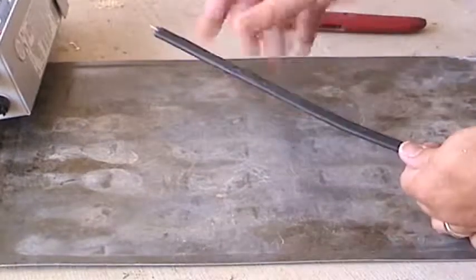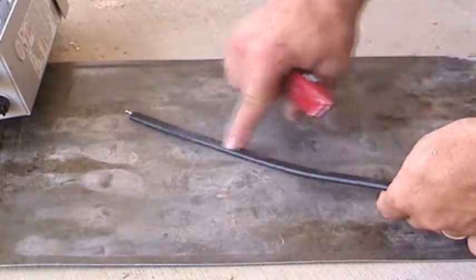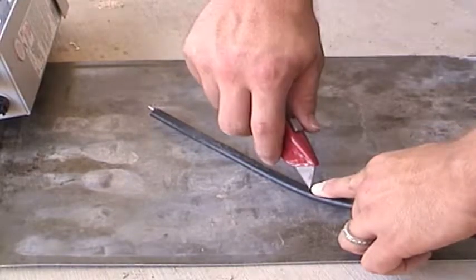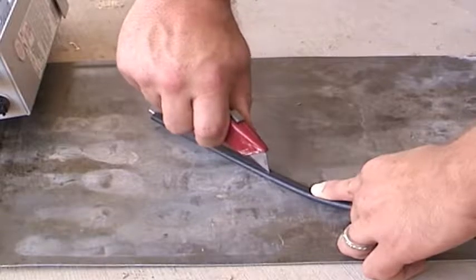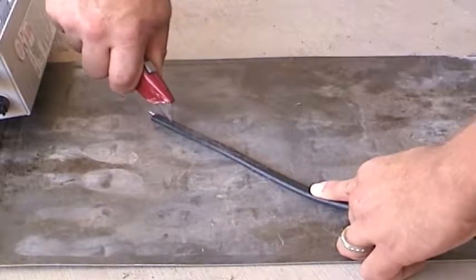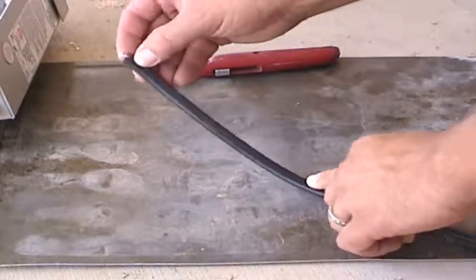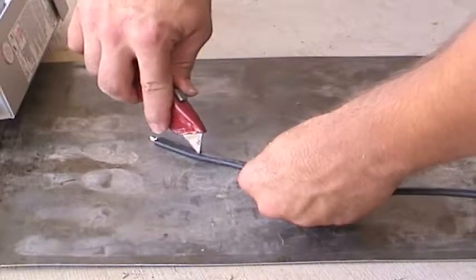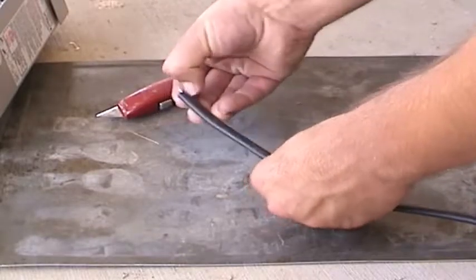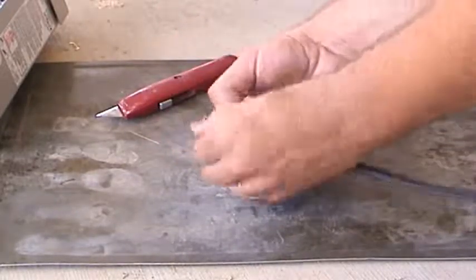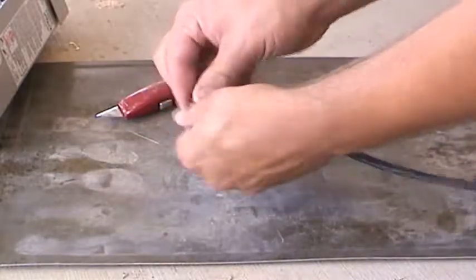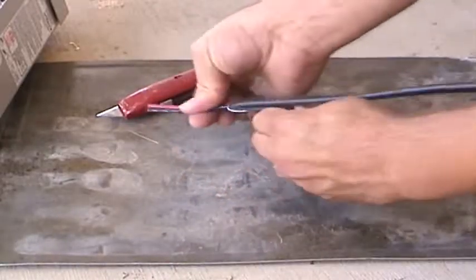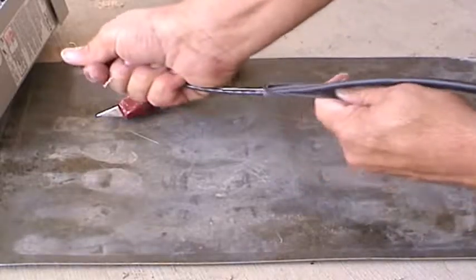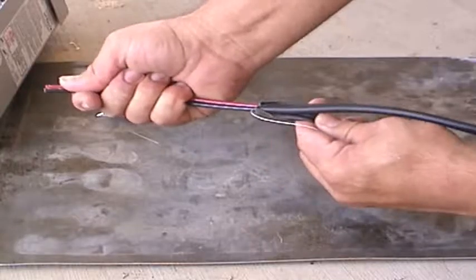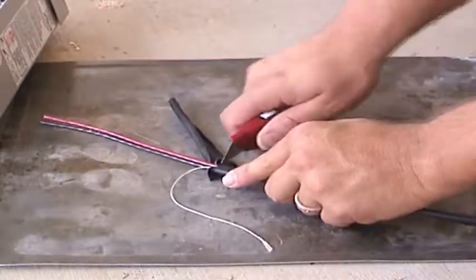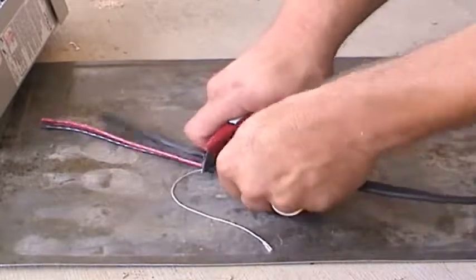Now let's grab one end of the 2-conductor outdoor cable and let's remove about 8 inches of the outer skin. We'll do that with our utility knife. Cut down the center of the cable. Be careful not to cut through to the other 2 cables inside. Peel back the skin until we've got about 8 inches of it pulled down. And then let's just cut off the last little bit.